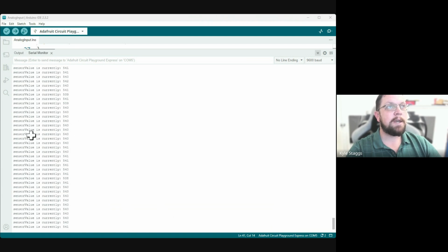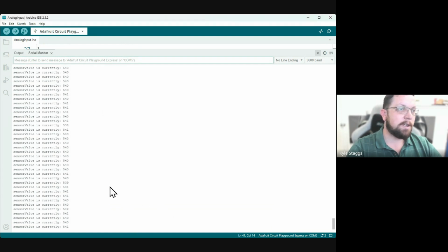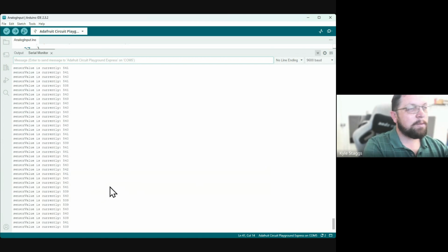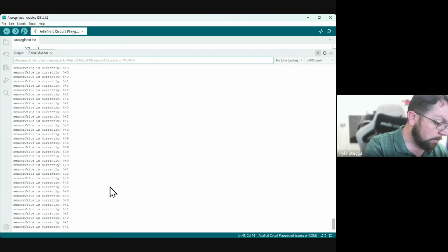And you'll see as we go to graph this why this will make some sense. I'm now going to do the alcohol saturation one more time to give me a third point for this calibration. If you've only got 2 points on yours, that's okay. 3-point should theoretically be a little bit more accurate and a little bit broader range. So I'm going to set it to where it can drain off the board without running onto the cable itself.